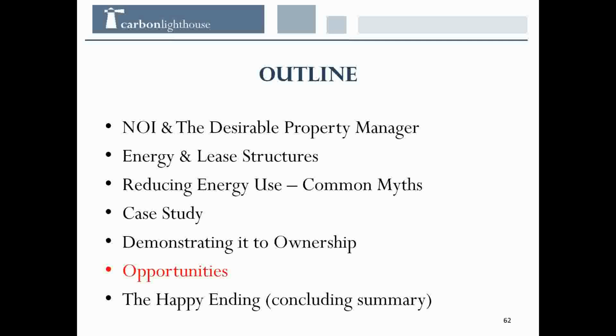If you're in the San Francisco Bay Area and you're looking at a building that has one chiller providing cooling to 3 different air handlers, that chiller might only run 200 hours a year. So even though it might be a big 500-ton chiller, it's still unlikely to give you a really good project. So I think it depends on a whole lot of factors, and you just need to get comfortable with them in your region and see the results of doing projects and see what savings come from doing what. So high utility rates make projects easier. Inclement weather makes projects easier. Long operating hours make projects easier. Hopefully that was helpful.